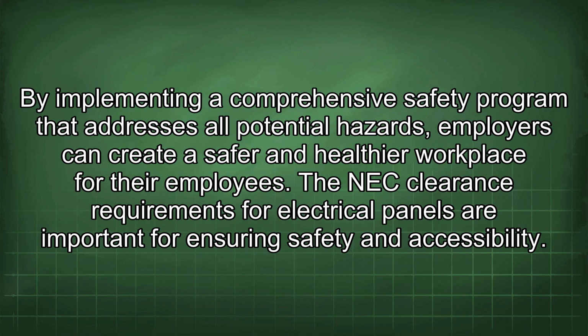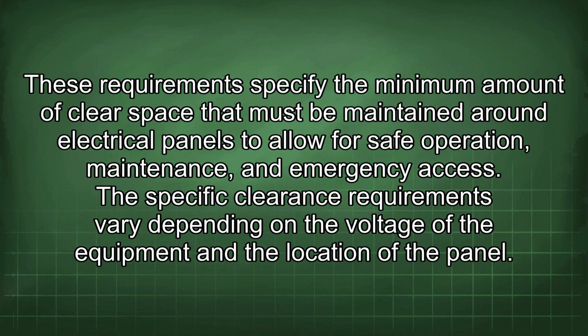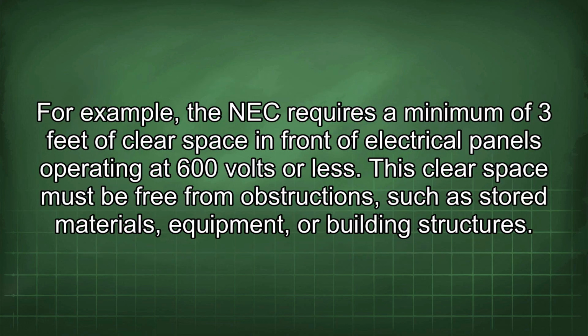The NEC clearance requirements for electrical panels are important for ensuring safety and accessibility. These requirements specify the minimum amount of clear space that must be maintained around electrical panels to allow for safe operation, maintenance, and emergency access. Specific clearance requirements vary depending on the voltage of the equipment and the location of the panel. For example, the NEC requires a minimum of 3 feet of clear space in front of electrical panels operating at 600 volts or less. This clear space must be free from obstructions, such as stored materials, equipment, or building structures.